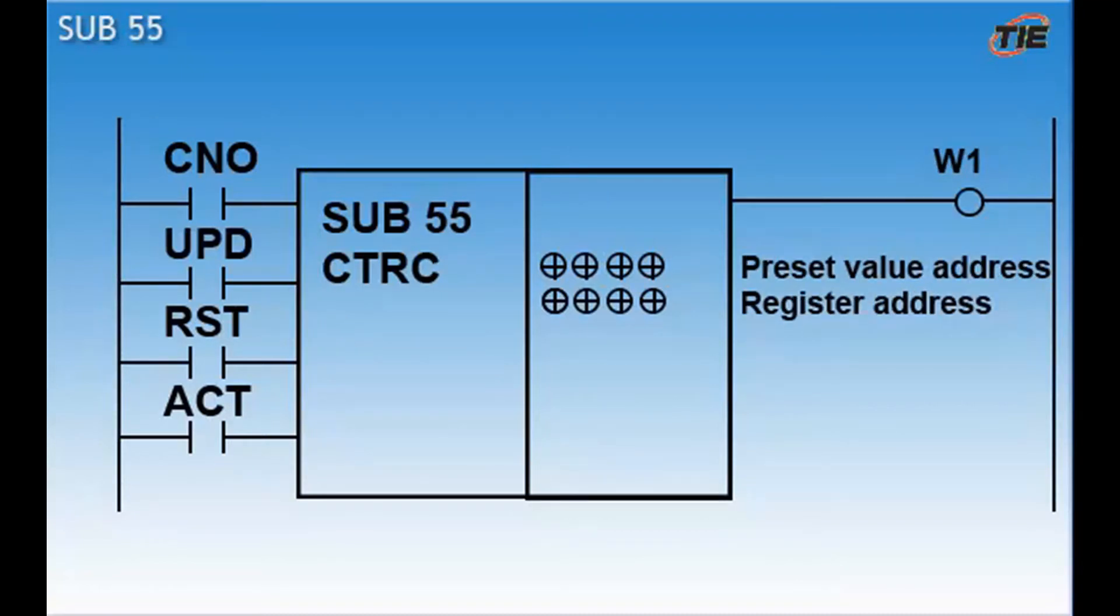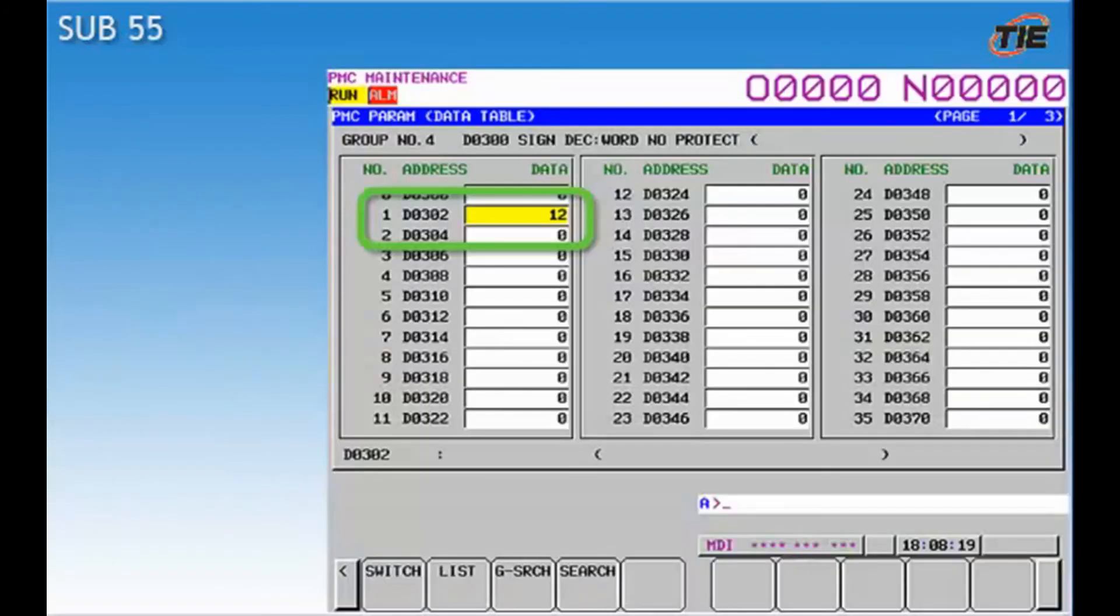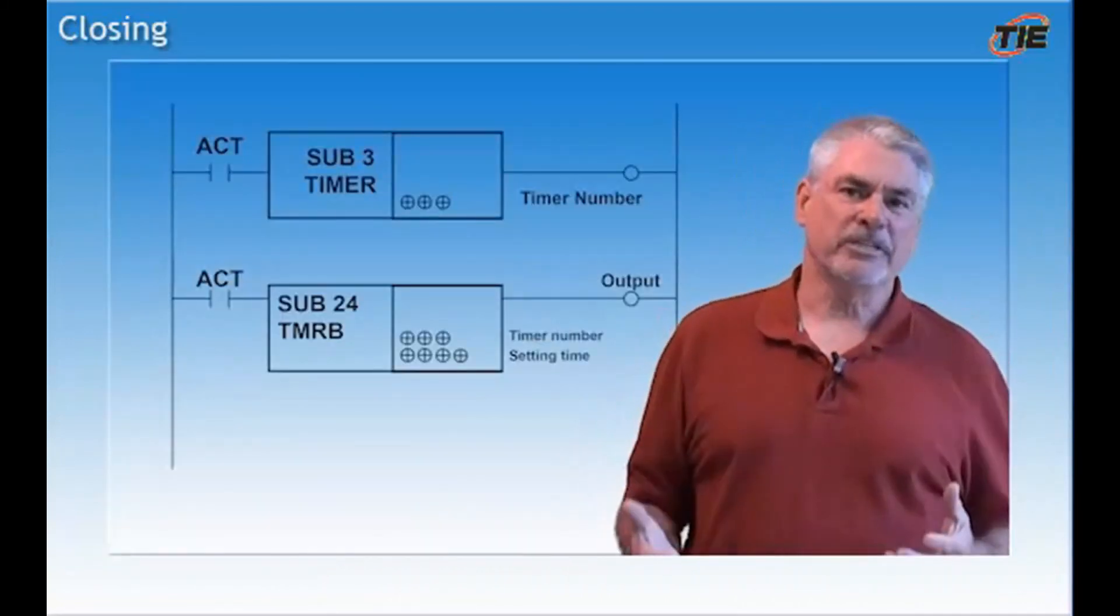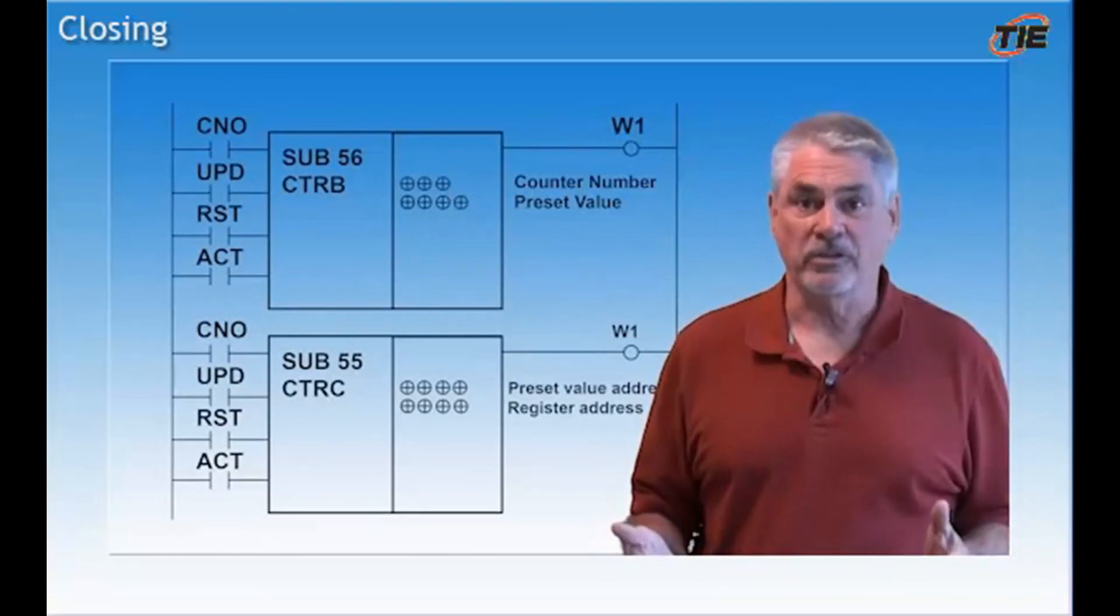The last counter we're going to talk about today is the CTRC, the sub 55. This is similar to the TMRC timer. The preset value for this counter is assigned to an address instead of having a constant value. The value in this address is often set in the data tables. For instance, by setting a value of 12 in data address D302, the counter is set to 12. All of the settings are the same as we discussed previously. This is a simple explanation of some of the timers and counters used on a FANUC control.